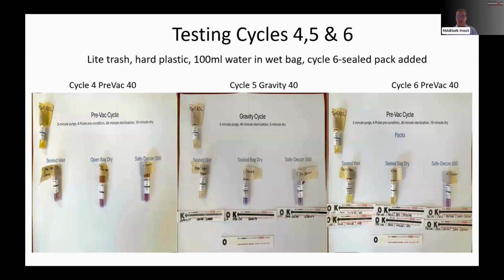So now I'm going to run the light trash, and I didn't put much trash. I filled the capacity of everything, the same amount of trash in the bags at 10% trash in it. And it replicated basically the same waste that you would have in your labs. So this had 10% capacity on the bag, not much trash. This is where things start, even with just a little bit of trash, start going downhill quick. I ran the pre-vac, the bags burst. This was an open bag and this was a sealed wet. Purple's good. We love to see it.